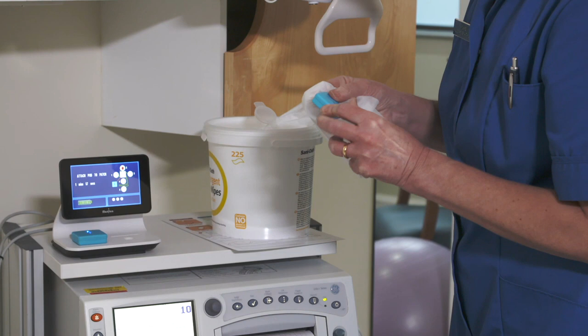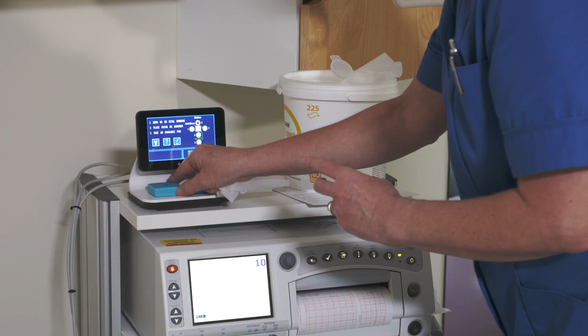Training Session 10. Cleaning. Wipe the Novii interface, Novii pod, and interface cables with a soft, non-abrasive cloth or disposable wipe soaked in aqueous detergent or disinfectant, or other solution such as 70% isopropyl alcohol. And then, it is good practice to use sterile or distilled water to remove the cleaning solution residue before drying thoroughly with a sterile soft towel or gauze surgical sponge.